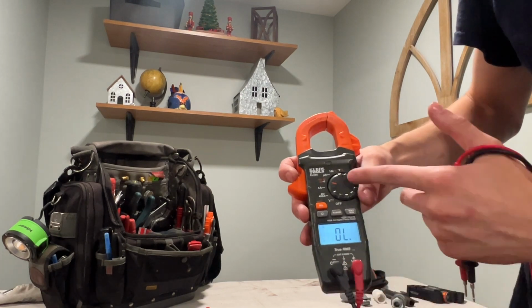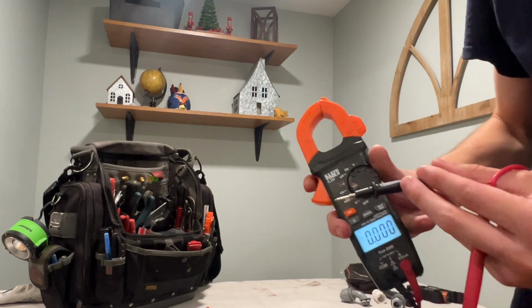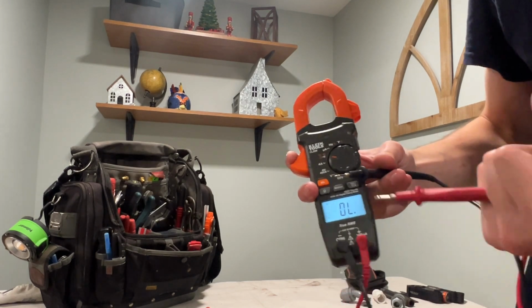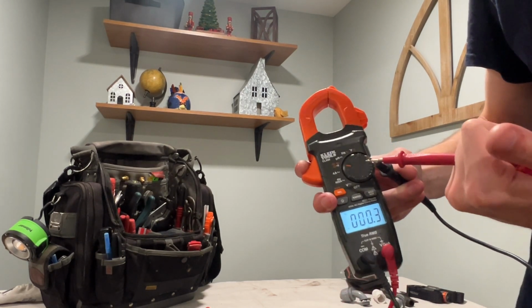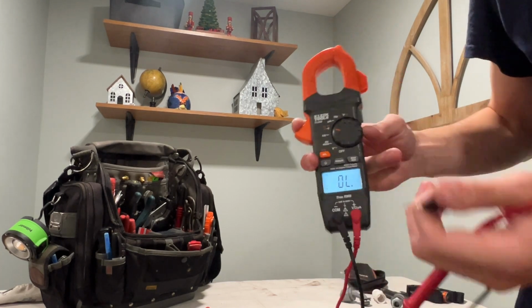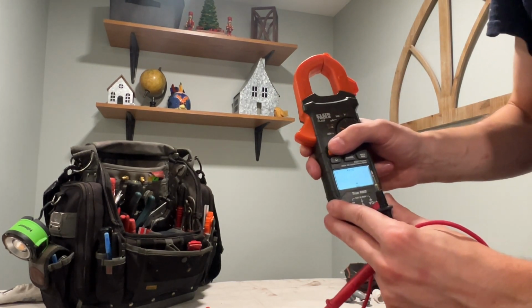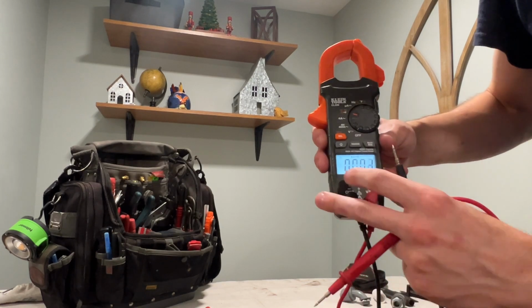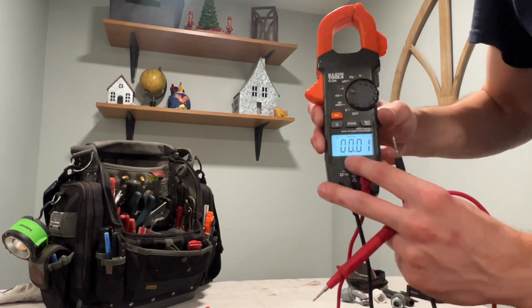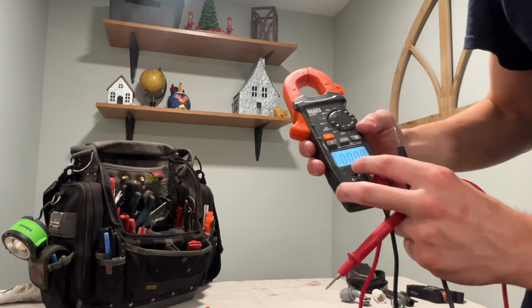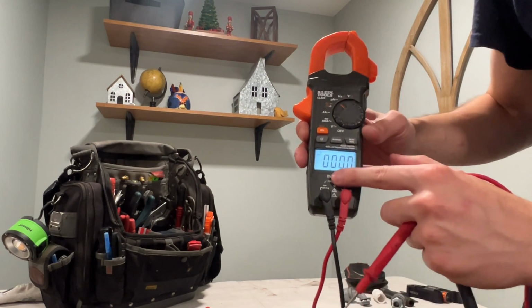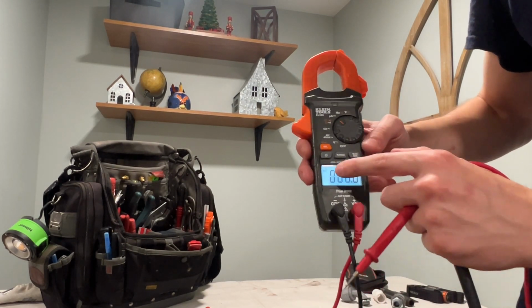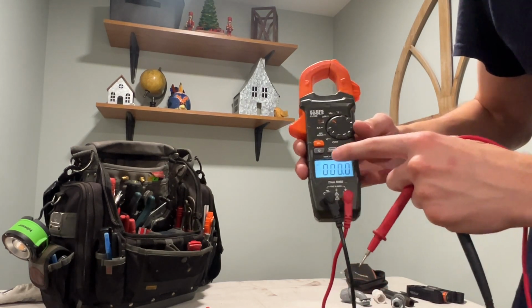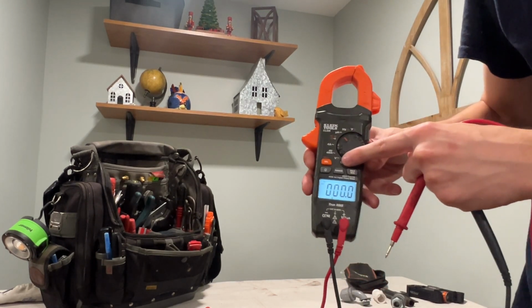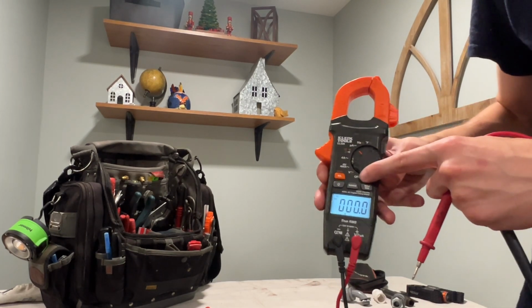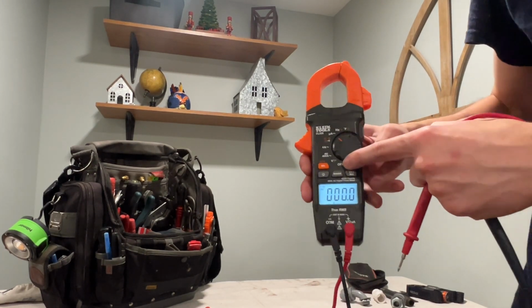You have your ohms, your continuity, so if I touch my leads together here while on ohms, it'll read continuity, little to no resistance. That's also where you'd go for all your ohm readings, plus microfarads and nanofarads for your capacitors. You can read microamps as well, for flame sensors, which would be DC microamps. In the volt section you can also read millivolts, and it'll automatically select, so things like thermocouples and thermopiles I have no issue with.